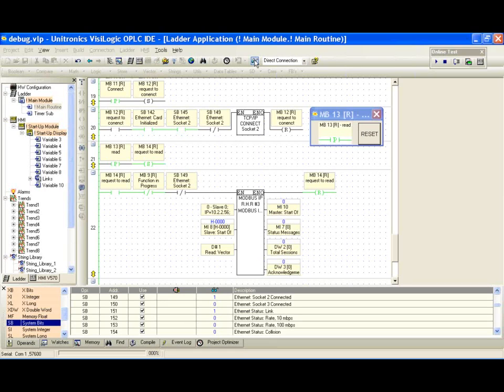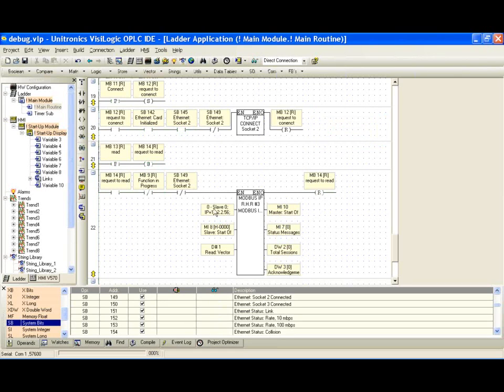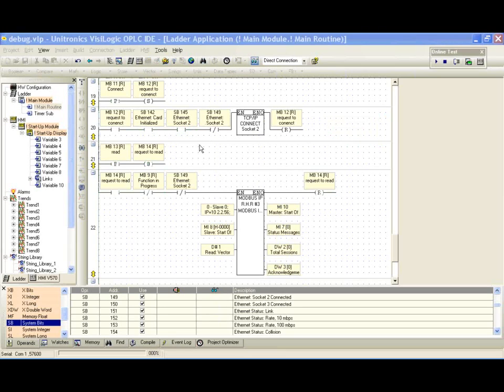Okay, so in my haste as a programmer, trying to run through functions I've created hundreds of times, I've made a mistake. If we want to look at the mistake, notice that we used SB149 above here as a normally closed contact. What that means is it's only going to be activating this network if it's low, but we see now we have it in net 22 as well, SB149 as a normally closed contact.